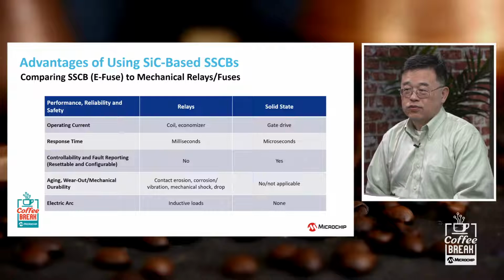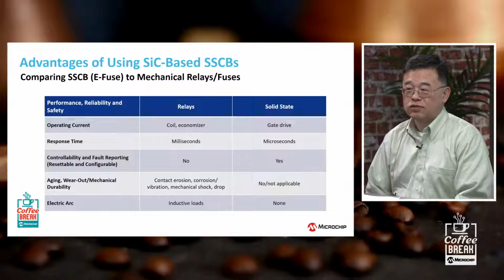Whereas the silicon carbide switch is very low energy. Typically it switches so fast, in the hundreds of microseconds versus the hundreds of milliseconds that a regular switch does, that you can detect that very low energy. So when it does switch and detect a fault, there's no arcing because the let-through energy is so low compared to what you'd see in a traditional relay or switch.